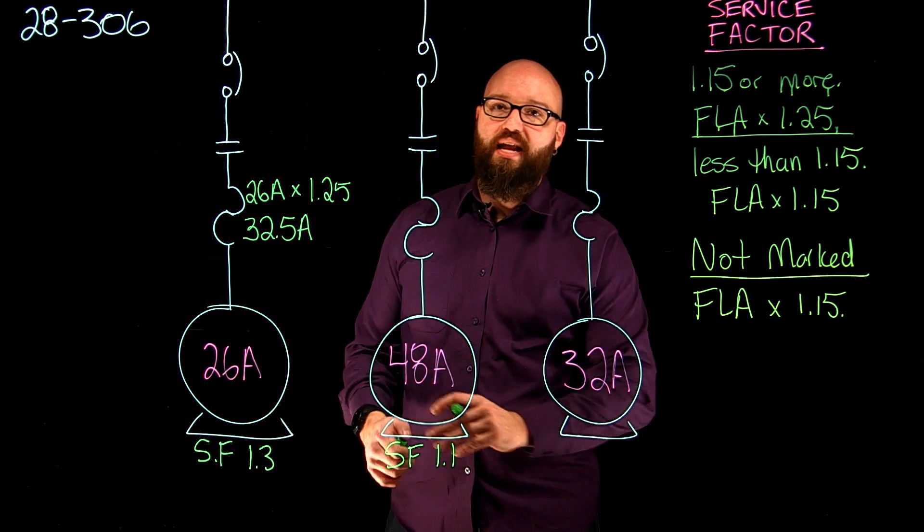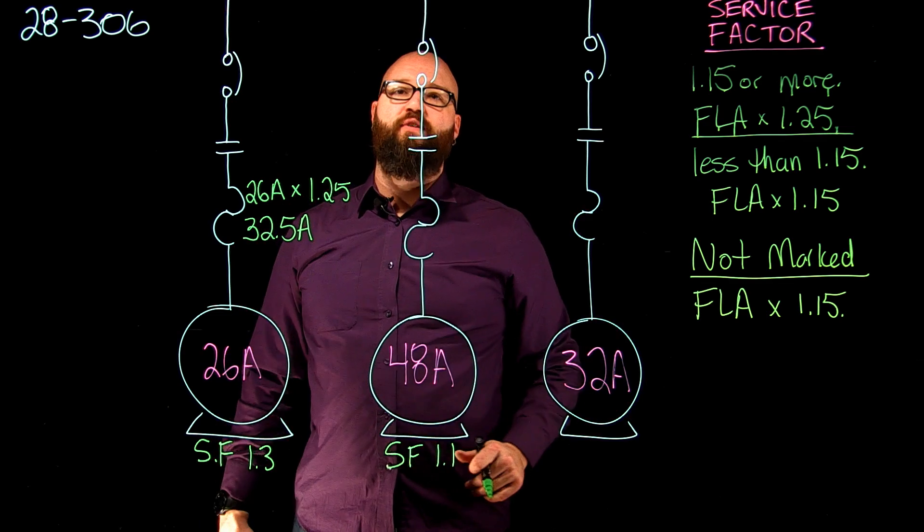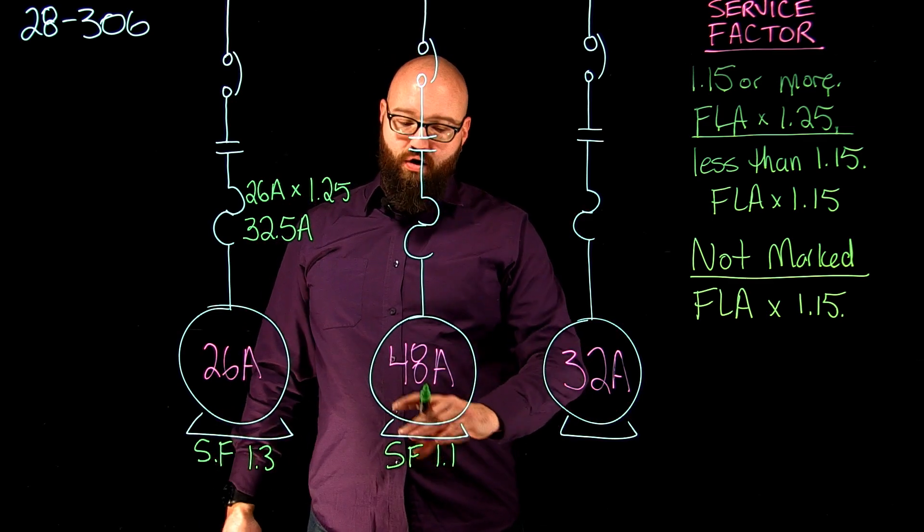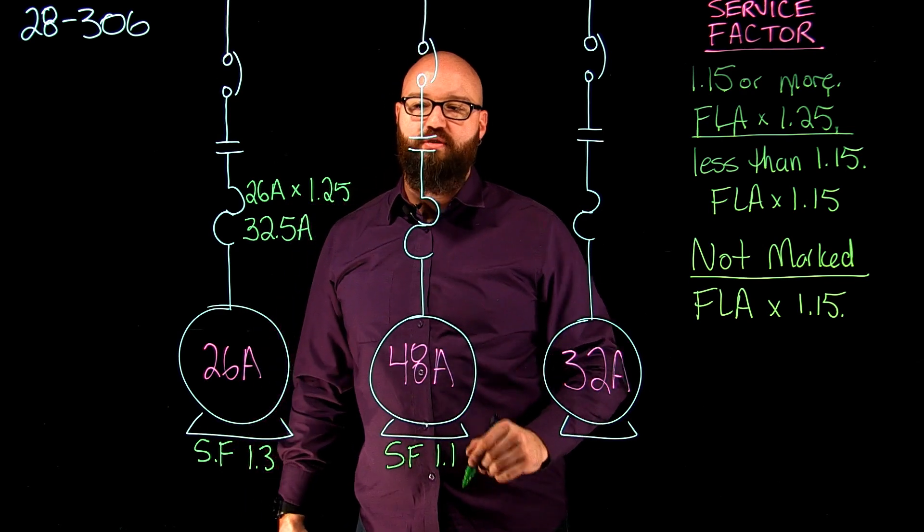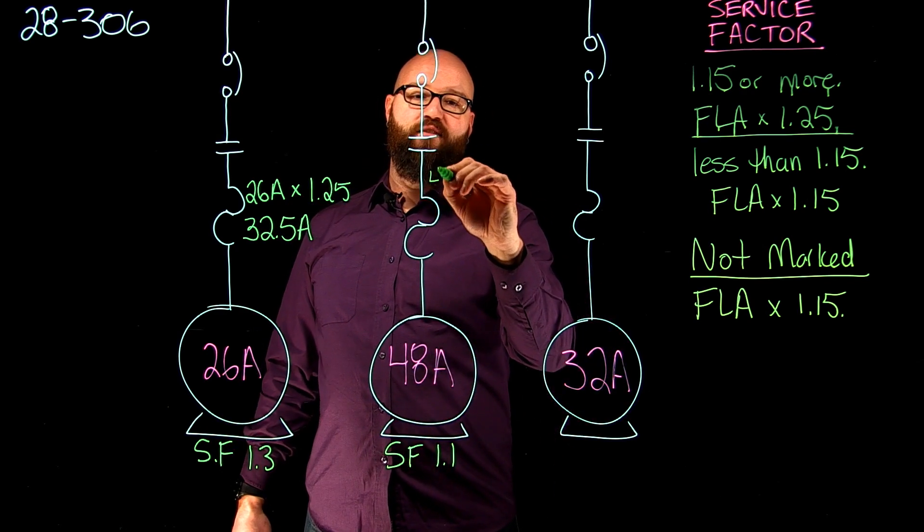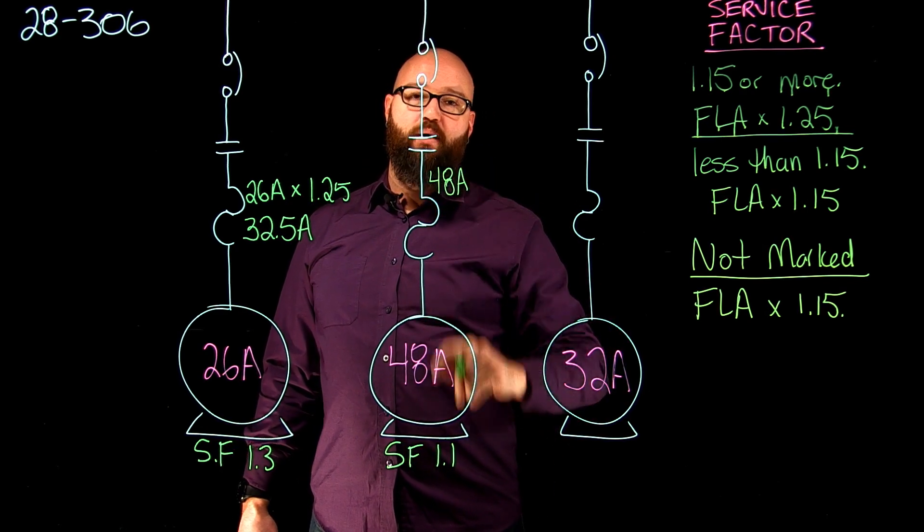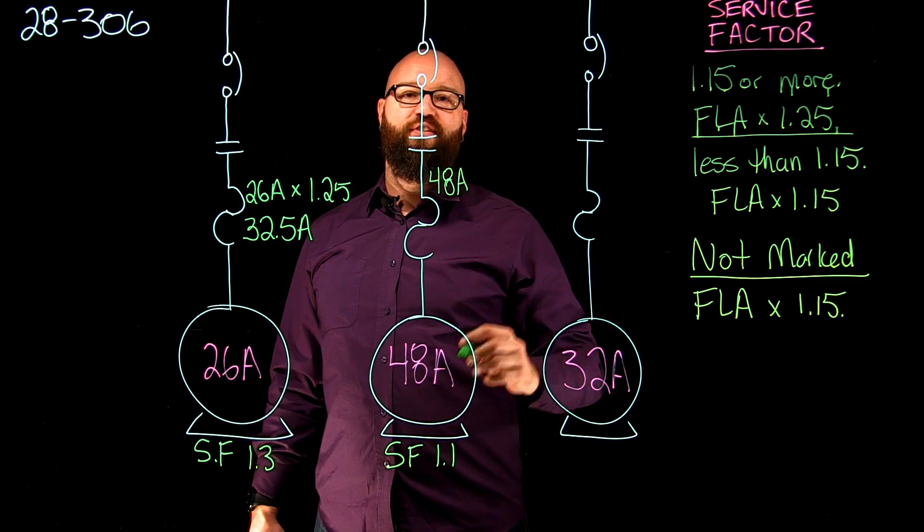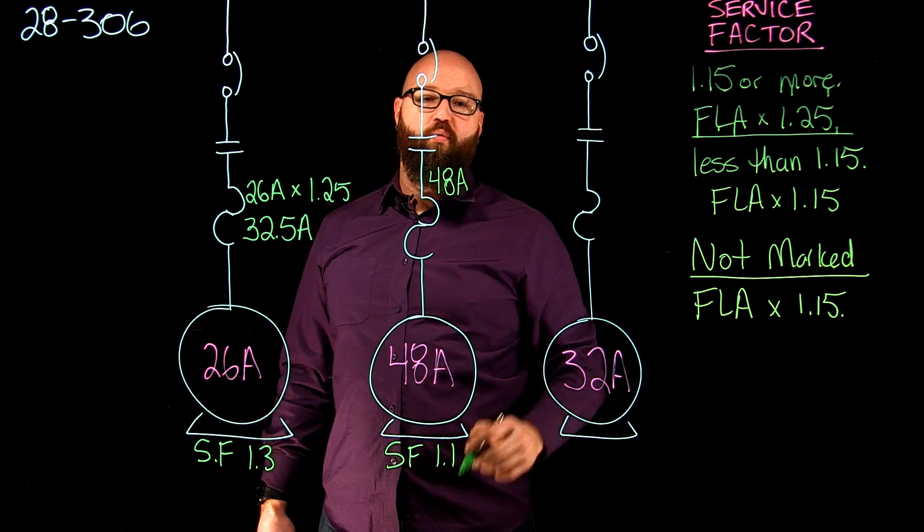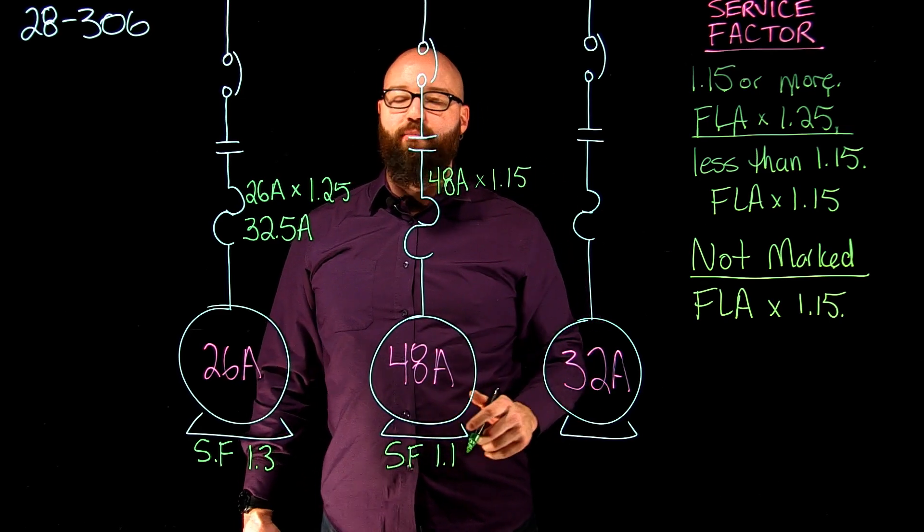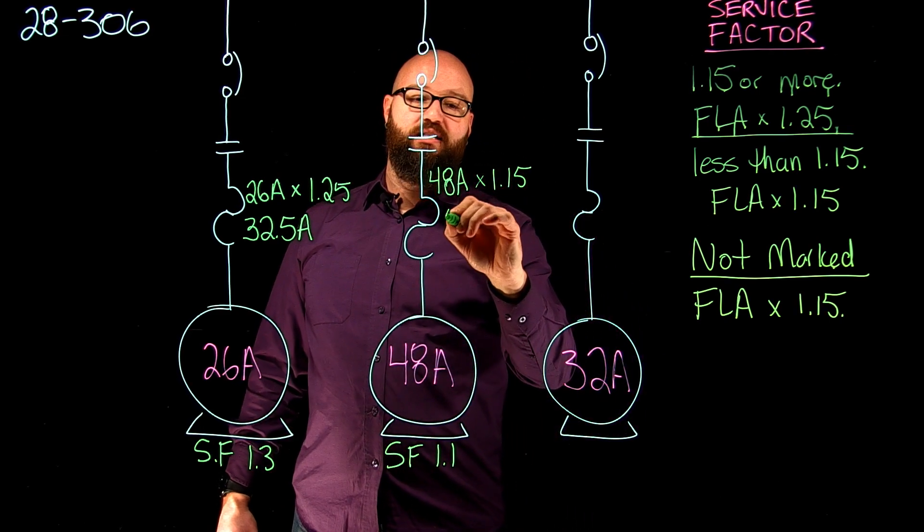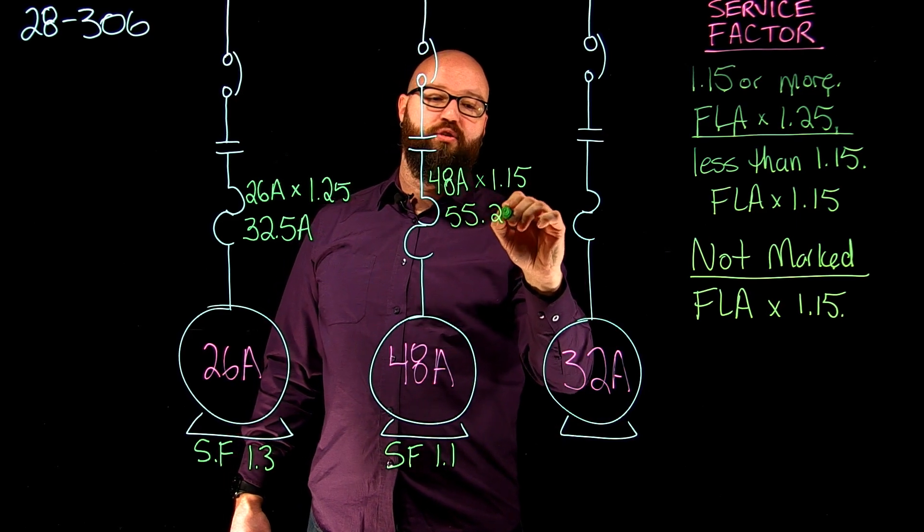Our second motor we have 48 amp FLA and a service factor marked of 1.1 or 110%. So again, using what we've talked about in 28306, we're going to take our FLA of 48 amps and multiply it by that 115% because again it's under 1.15. So times 1.15 gives us a maximum overload setting in this case of 55.2 amps.